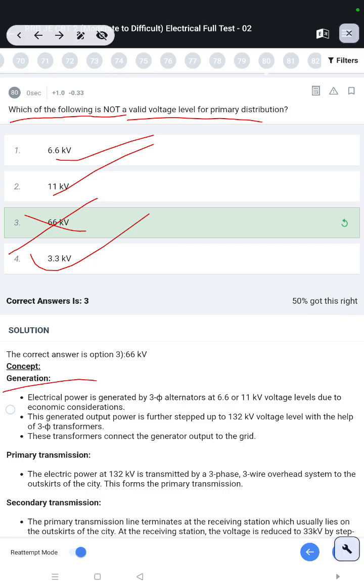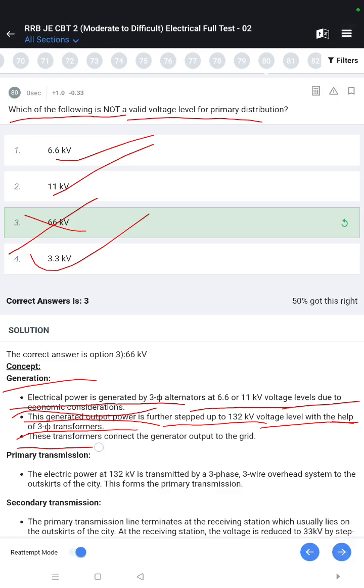देखिए कॉन्सेप्ट। Generation: electrical power is generated by तीन-phase alternator at 6.6 और 11 किलोवोल्ट वोल्टेज लेवल due to economic consideration. This generated output power is further stepped up to 132 kilovolt voltage level with the help of तीन-phase transformer. These transformers connect the generator output to the grid.